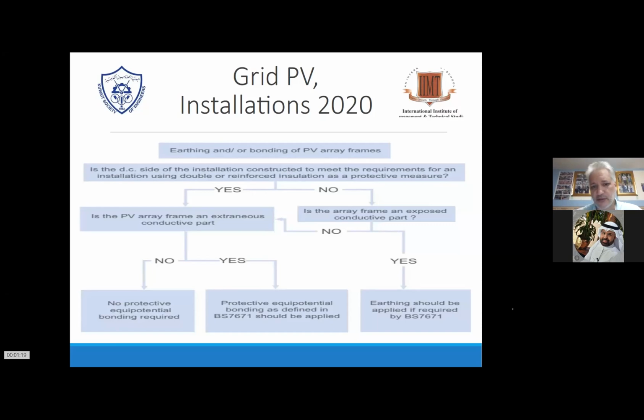Again, it has an historical impact. For example, in Germany, it was not needed to earth the structure. So we had, of course, the transformer-based, where you don't need it anyway. And then you have the rails. After 2008, the transformerless inverter came up. Then just out of personnel maintenance and security and health and safety, they decided to earth the structure in case we have the 30 milliamps leakage rule, that there is a problem while you take off the module. You could get shocked. In UK, it's a touch and step voltage.